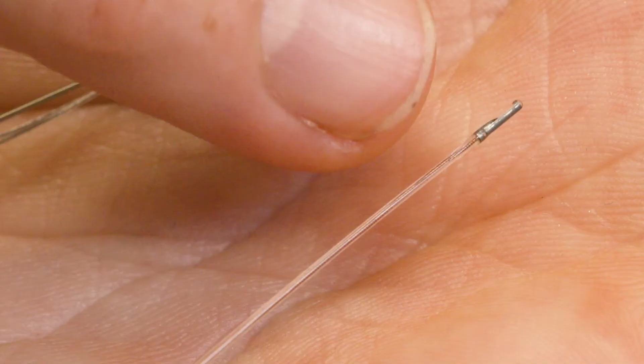If you've been used to working with the fluid-filled catheters and you switch to the solid state, you'll notice what you're seeing on the screen looks a little bit different. That's actually real. What you're recording with these solid state catheters is a better reflection of what's happening inside the animal. You see usually a higher systolic, a pointier angle, and a bit more dynamic change throughout the pulse cycle. So you'll see a little bit more of a bump after the systolic peak, depending on where you're recording. If you're just looking at mean, it's not critical because, over longer periods of time, the mean level of pressure will be similar.